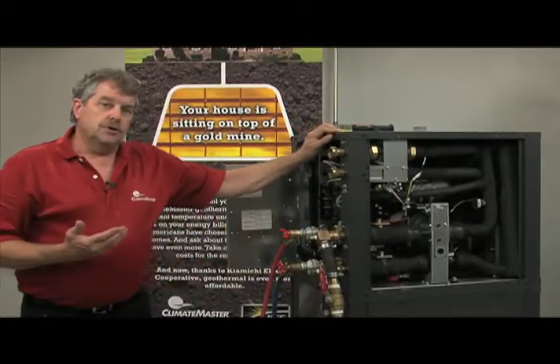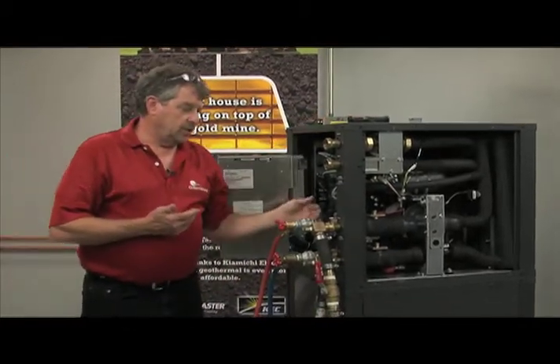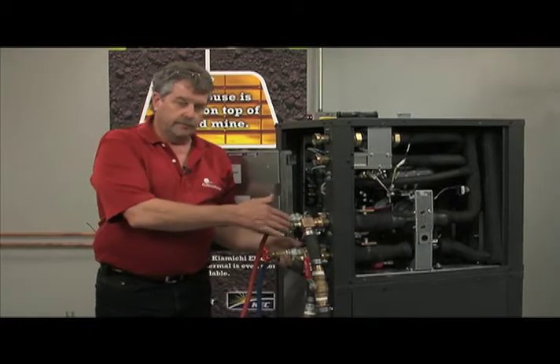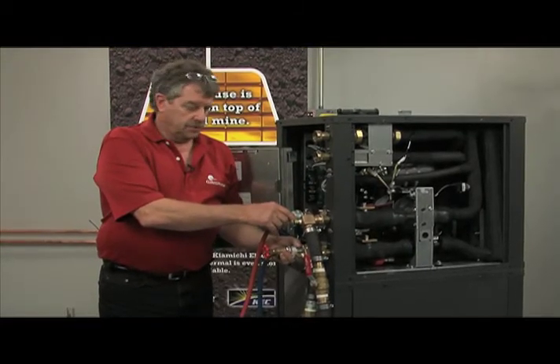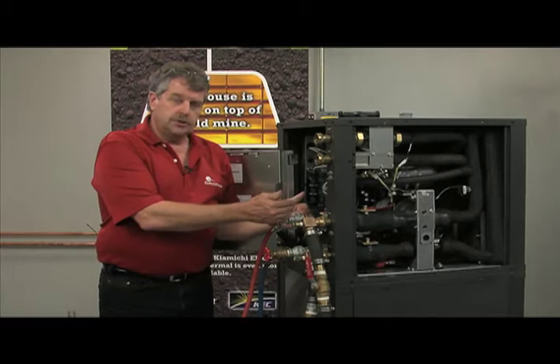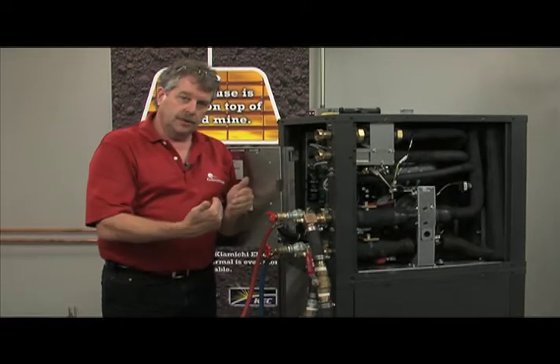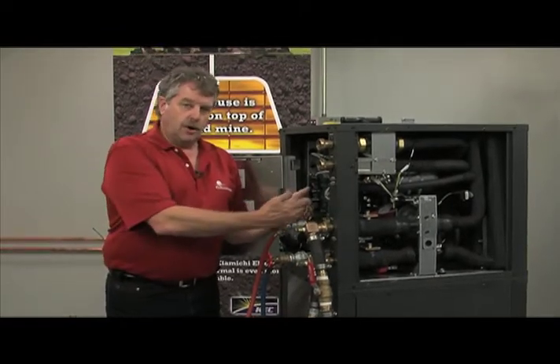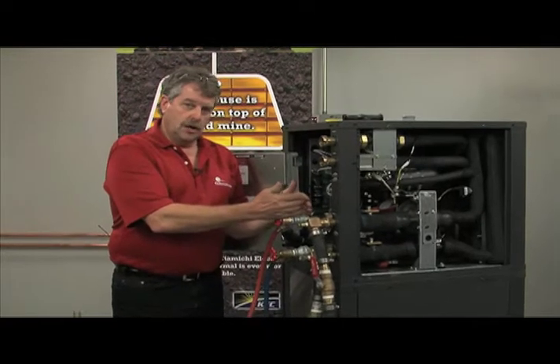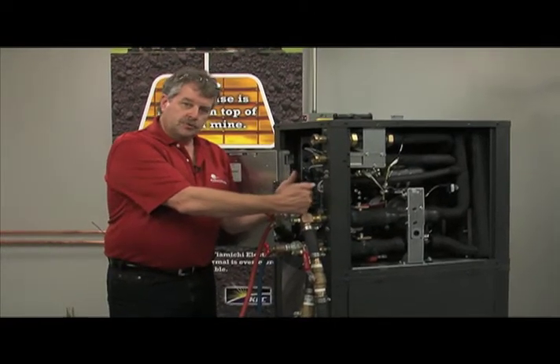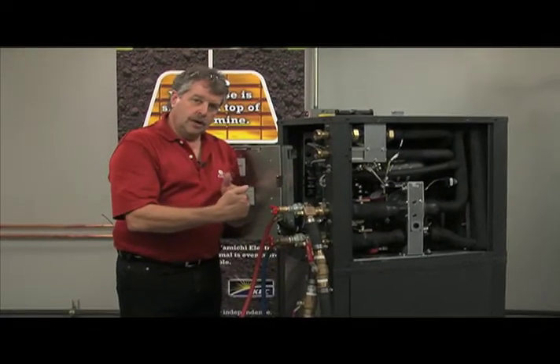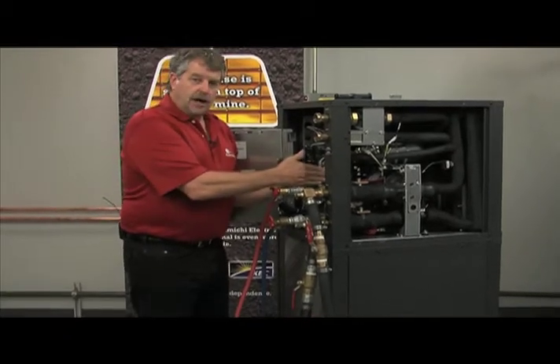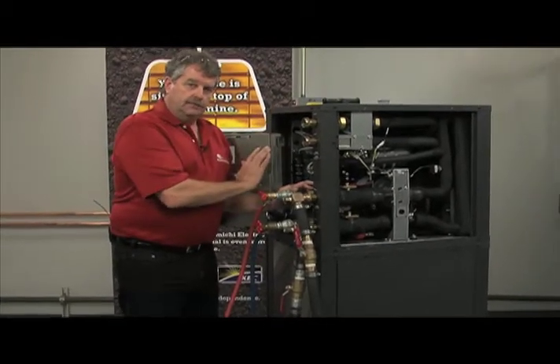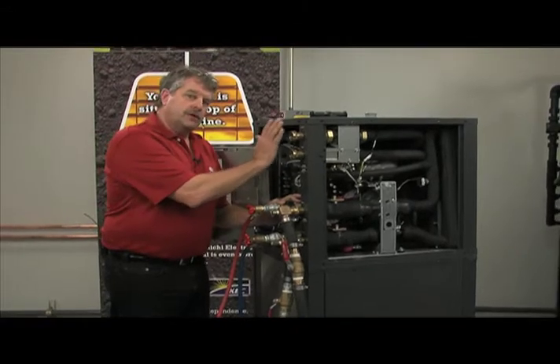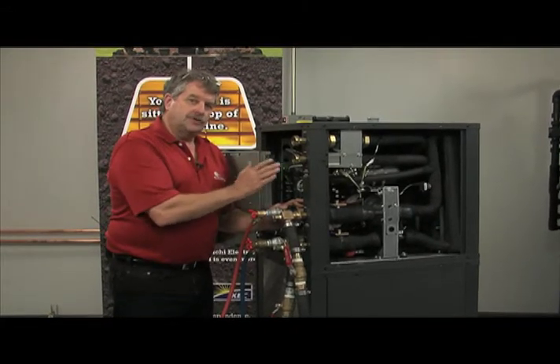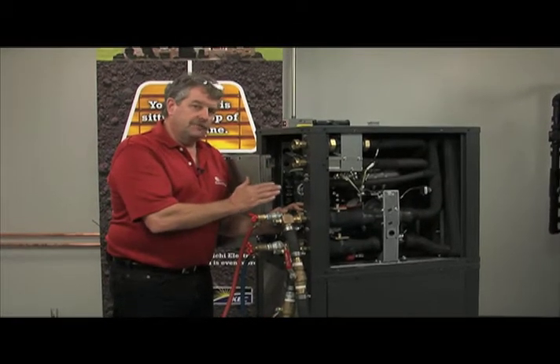The first thing you want to do is install some kind of boiler drain with short hoses so you can isolate the loop. You're going to rotate the flushing valves in here so that pressure is retained in your ground loop, but open to this valve is just the heat pump side - similar to when you were going to flush just the unit, that's the orientation you put both valves in.